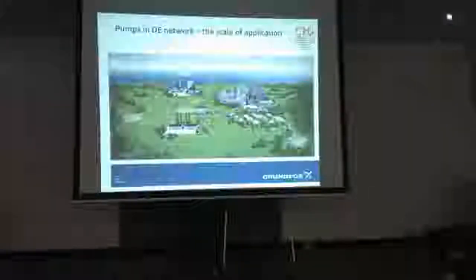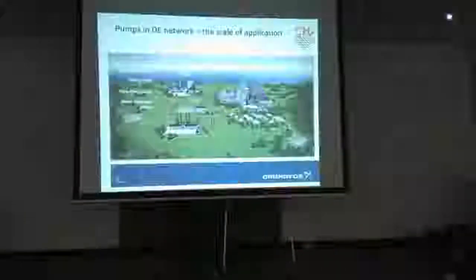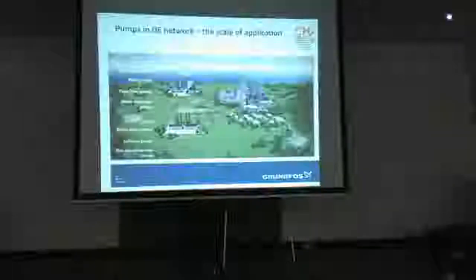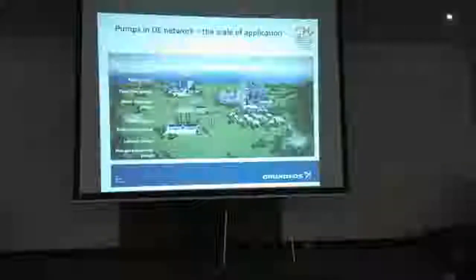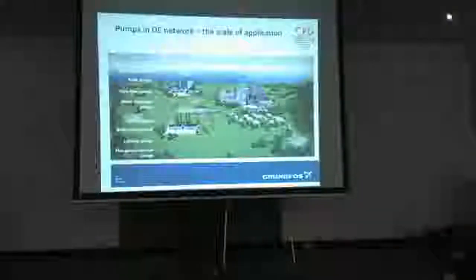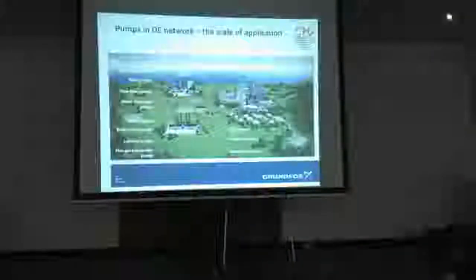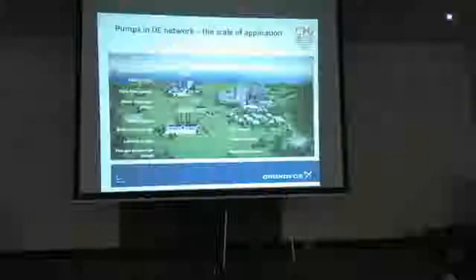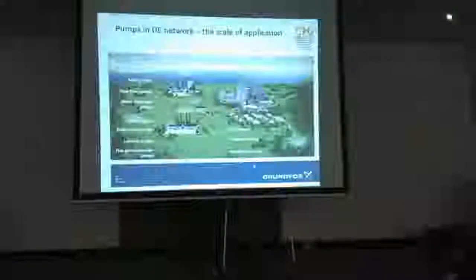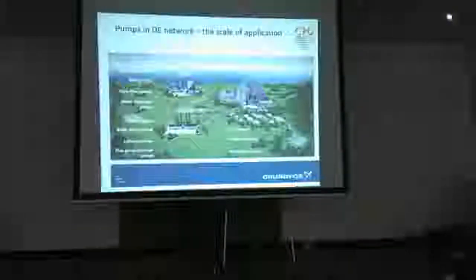So, pumps in the network, where are they? Stating the obvious, really, I suppose. You've got your main power plant, there's main distribution pumps, filtration pumps, water treatment pumps, chemical dosing and so forth. Then you've got maybe another boiler house somewhere or other, shunt pumps, low temperature heating pumps there, economiser pumps, flue gas, getting the heat back out of the flues. And then you get out into substations where, in our language, this is a sealed system pressurisation set type of pump equipment. More distribution pumps sending it around different legs of the network.